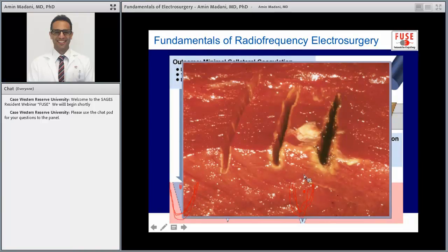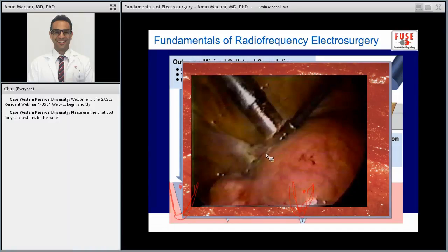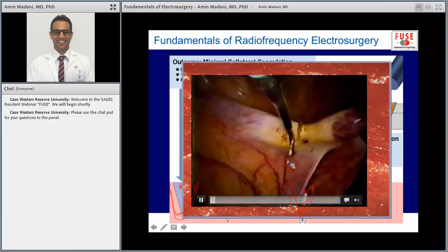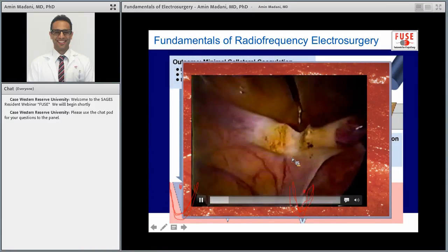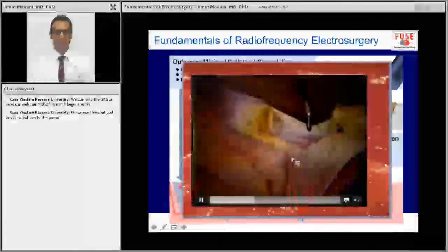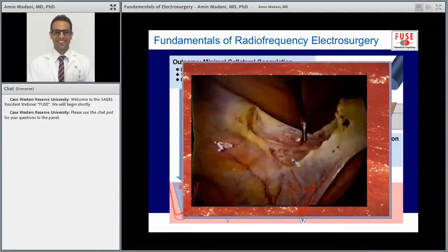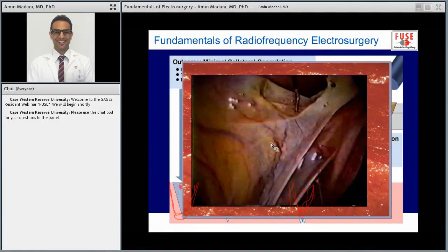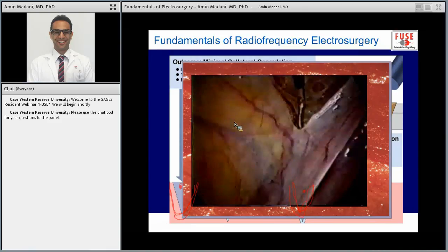So the answer here is to just use cut and coag smartly and cater it to what you want to do in the operating room. As demonstrated here, they're using a cut waveform, and you can see there's very minimal collateral thermal spread. You can do this for hemicolectomies if you're in an avascular plane. You don't necessarily need to use coag. It can increase your rates of injuries and collateral thermal injuries. A lot of bile duct injuries are caused because of that as well.